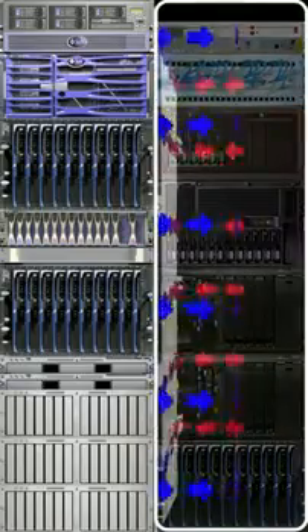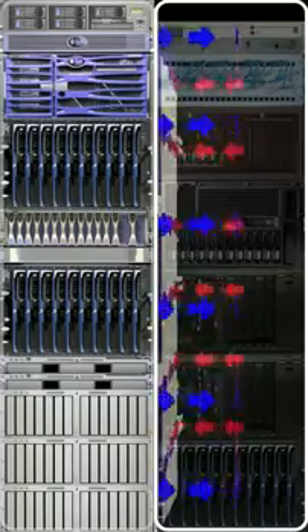It's been specifically designed to blow cool air across the whole height of the enclosure to ensure that there's no chance of having any hotspots developing. This is a closed-loop cooling system, which focuses the cooling directly where it's required, physically separating the hot and the cold air paths so they can never mix, also significantly increasing system efficiency.